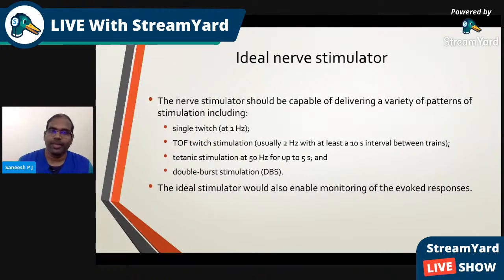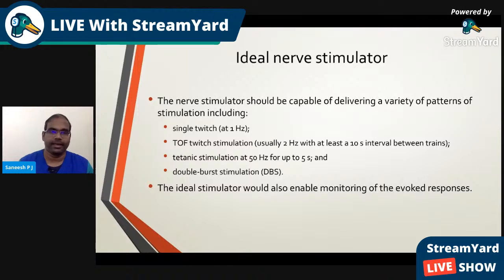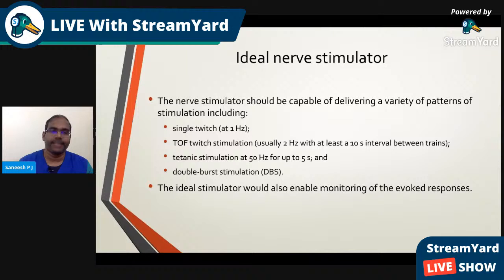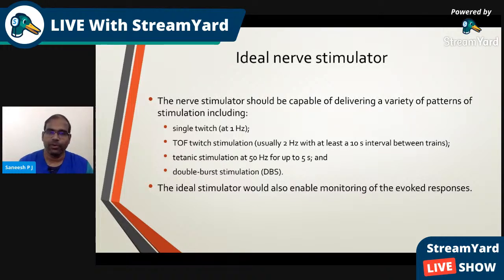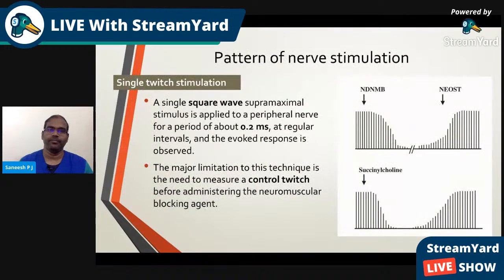The nerve stimulator should be capable of delivering a variety of patterns of stimulation, including single twitch at one hertz, train-of-four twitch stimulation at two hertz with at least a 10-second interval between trains, tetanic stimulation of 50 hertz for up to five seconds, and double burst stimulation (DBS). The ideal stimulator would also enable monitoring of evoked responses.